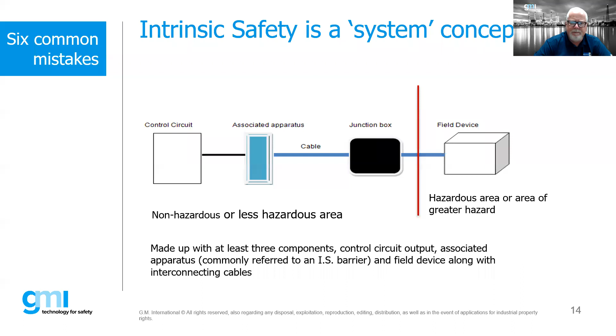We combine whatever our controller is, whether a PLC or a DCS. The associated apparatus is commonly referred to as our intrinsically safe barrier. The cabling is also part of this, as well as any junction boxes or marshalling cabinets, and finally our field device. It is a system concept, and we have to keep that in mind, especially when looking at potential faults and the selection of devices—we need to make sure they match and that they're safe.